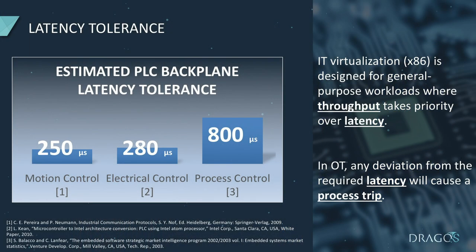There have been studies estimating backplane latency tolerance per industry. One of the fastest latency tolerances is the motion control industry — robotic arms swinging around need to be monitored at a very high frequency — so those are only tolerant at 250 microseconds. Electrical control is a little higher at 280 microseconds. And process control, like water systems or oil and gas, is much higher at 800 microseconds.